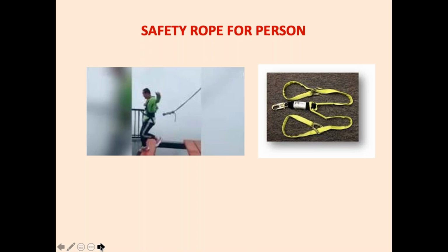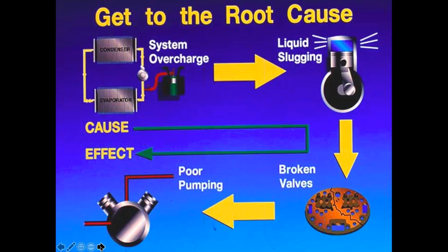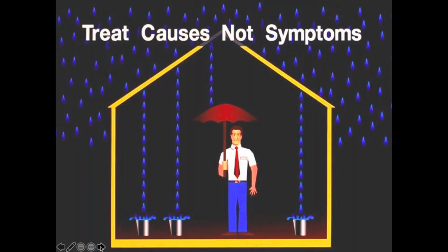This is my experience. An accident has taken place in which the person did not come out, another person entered, another person entered, and in a cold storage 3 persons died because of a heavy leak of ammonia. They entered inside the cold room without taking proper precautions. So this is very important. Get to the root cause. What is the problem? Very important. Don't treat only the symptom.